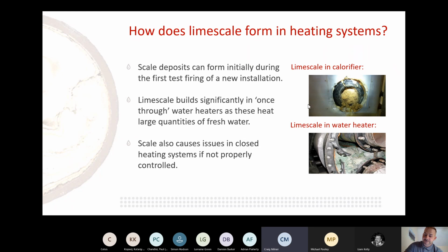One thing to note as well is, even with a top-firing water heater, lime scale still forms but falls down to the bottom, as shown there. It might not stop the water heater from working, but you're building up a level of lime scale at the bottom. What happens then is, since lime scale is a really good insulator, it stops the water in that area from heating up to 60 or 65 degrees, and then you could get a Legionella problem down at the bottom of the cylinder.